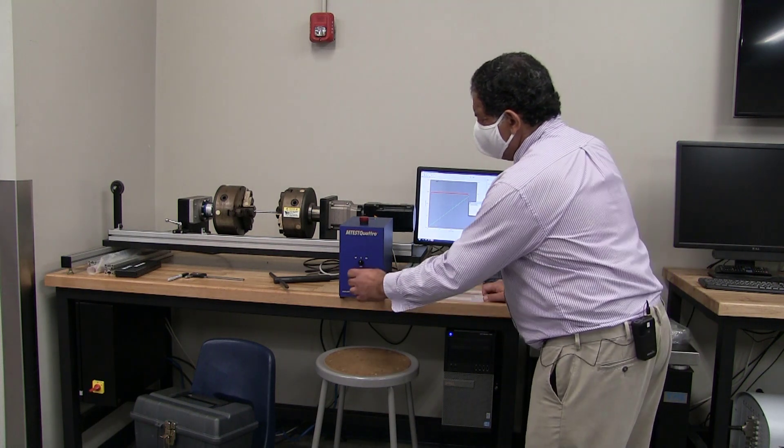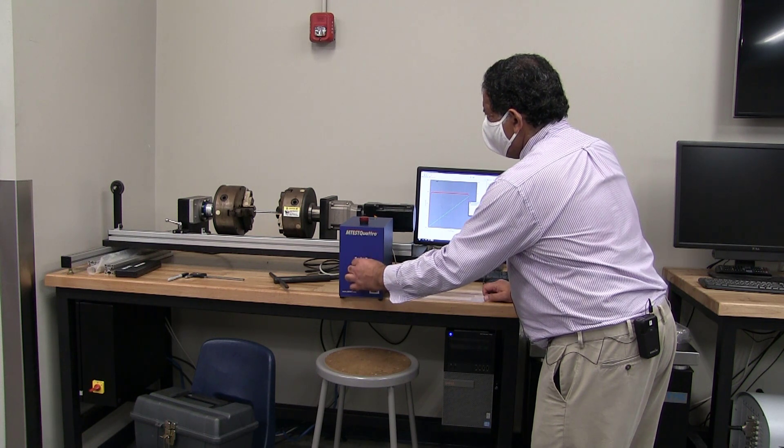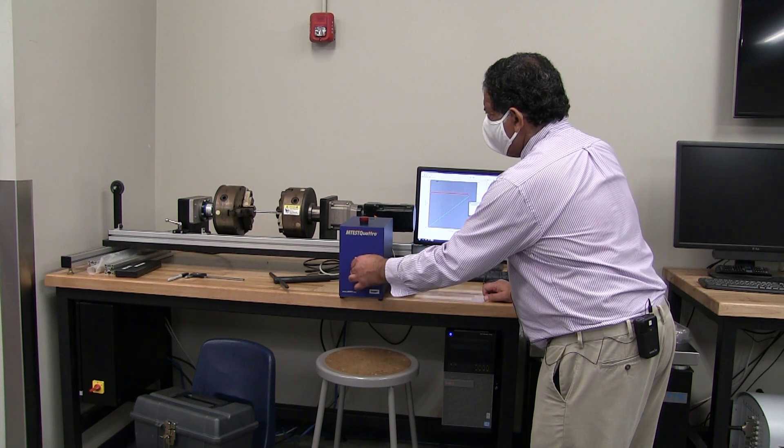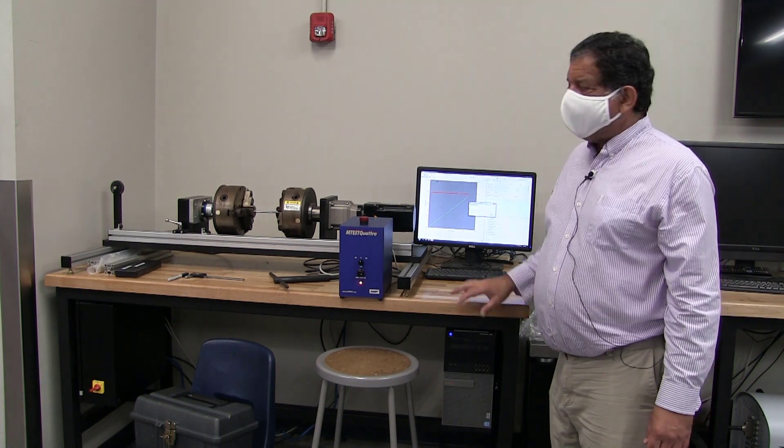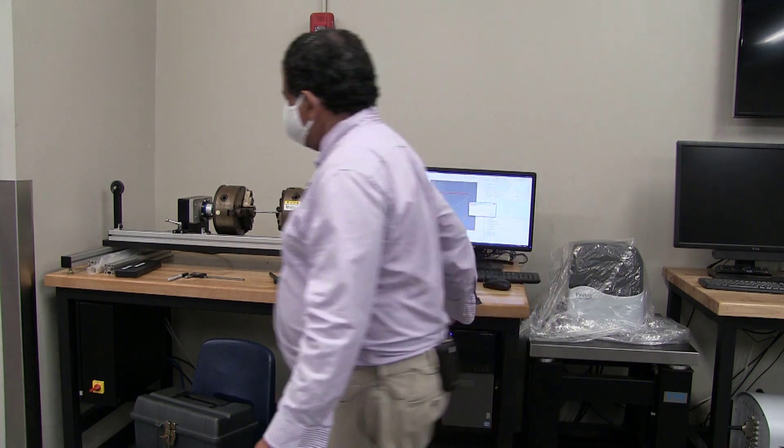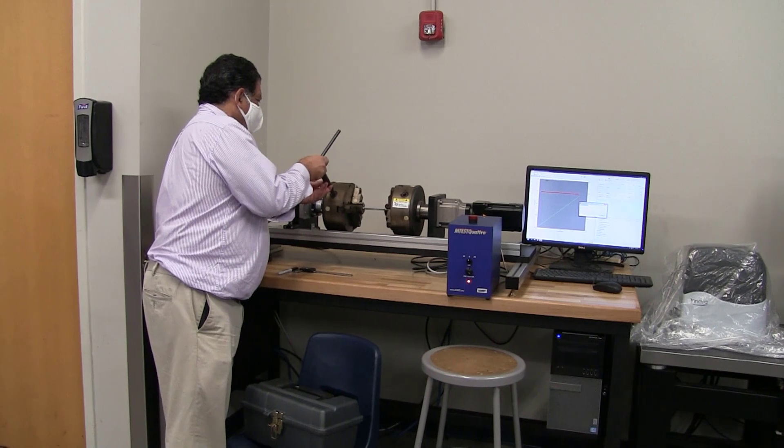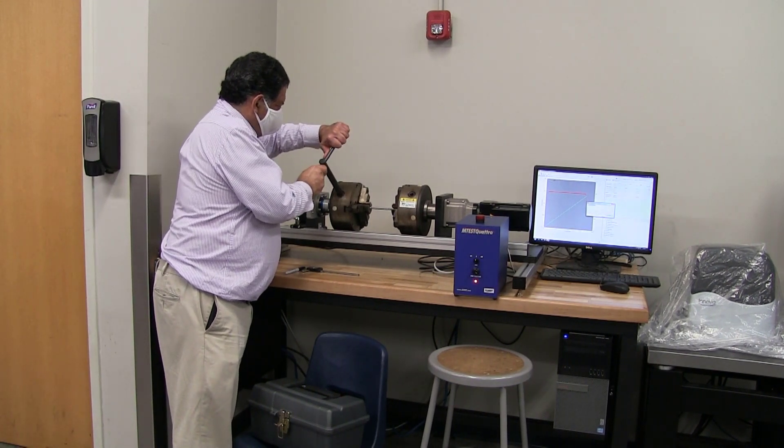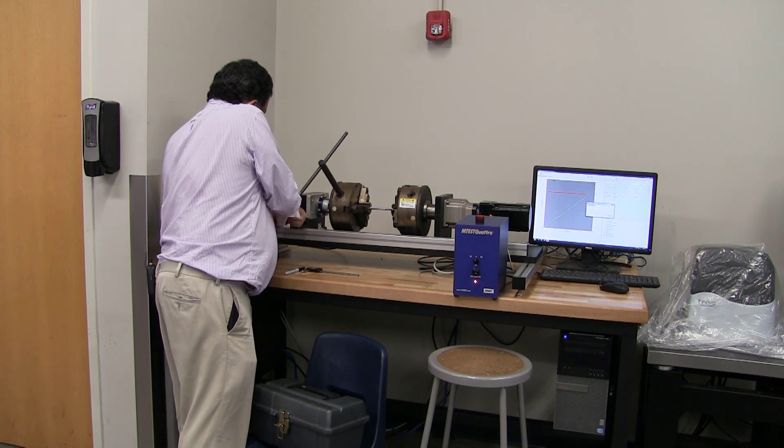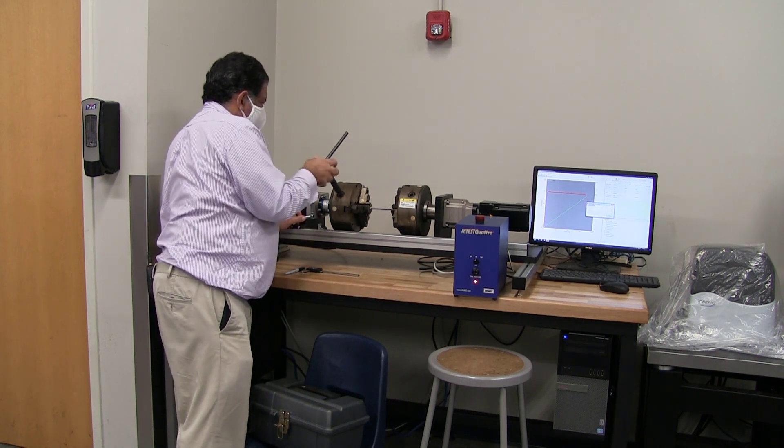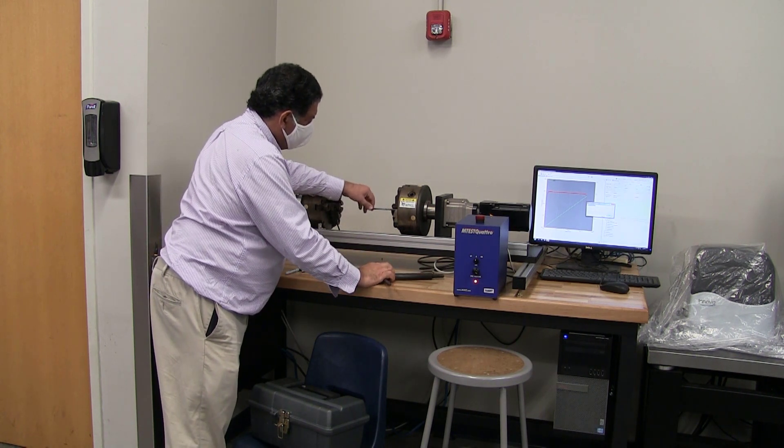Now, what I'm going to do is I'm going to continue to rotate it. There. Now, you heard that little click. That was when the last little ligament let go. So now, when I unload the specimen and remove it, you're going to be able to see the fracture surface.